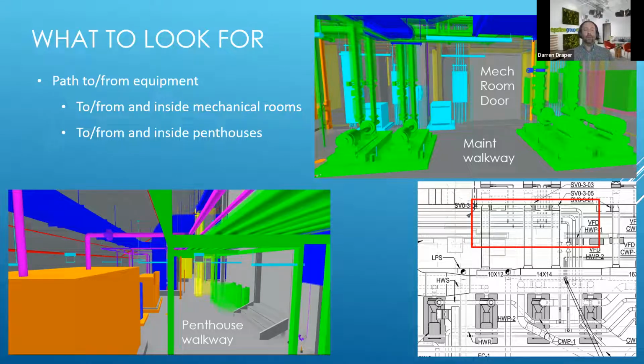So how are we getting to and from and around inside mechanical rooms and mechanical penthouses, for example. You see examples here where this penthouse walkway in the bottom left is actually a clear path. This light green is structural steel for mechanical piping flying overhead, and the spacing on that structure, both in height and width, is sufficient to allow an operations and maintenance person to walk through there, in this case with at least a dolly to load a small motor in and out through that pathway, ideally traveling the full length of the penthouse without things in the way.